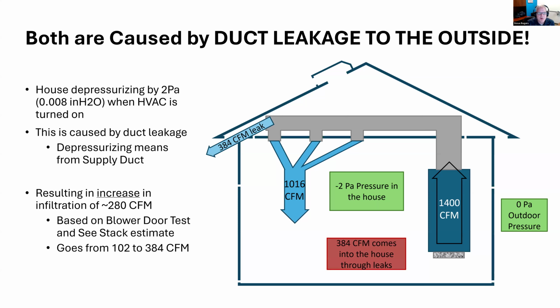And the reason they don't implode is because they have holes in them and the pressure will go down until the airflow is balanced. Now I've got 1,400 CFM leaving the house and 1,400 coming back in, because 1,000 is coming back in the supply vents, but the other 384 is getting sucked in every crack and hole and leak in that house, bringing in hot, humid outdoor air.